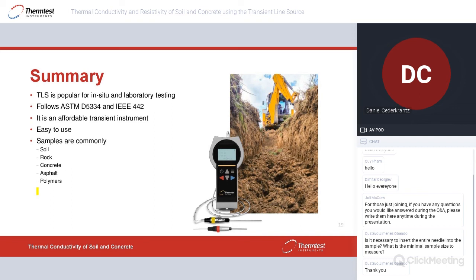It's an affordable transient instrument, very easy to use, and it can test a fairly wide range of samples. Soil, rock, concrete, asphalt, and polymers being the most common ones, but we have also seen testing of, for instance, wood and other types of samples. So it has quite a lot of potential in a small frame.